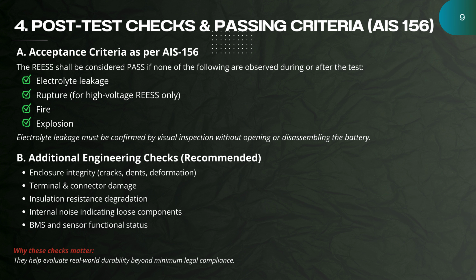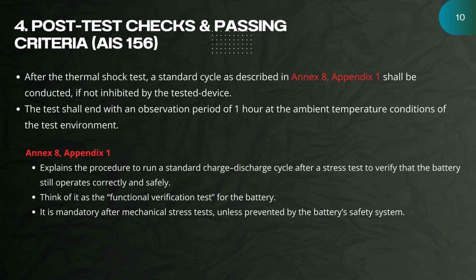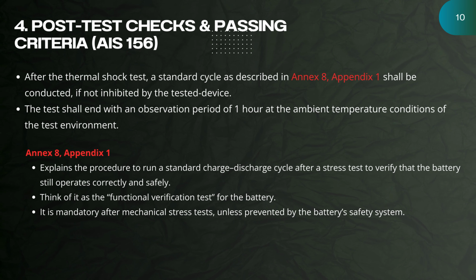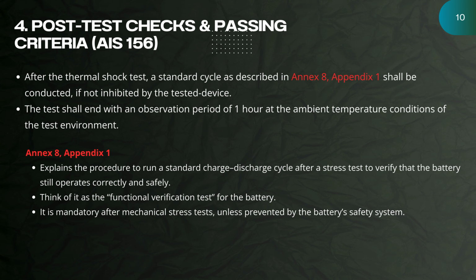Beyond the mandatory criteria, we also recommend checking for casing cracks or deformation, connector and bus bar loosening, any cell displacement inside the pack, and BMS functionality. These aren't legally required but are critical for real-world reliability. After the shock test, a standard charge-discharge cycle as per Annex 8, Appendix 1 needs to be done unless the BMS prevents it. This is basically a functional health check to confirm the battery still works correctly after the stress. The test ends with a 1-hour observation period at ambient temperature, watching for any delayed leakage or thermal events.